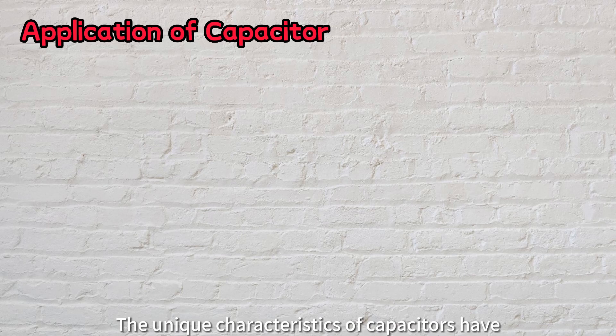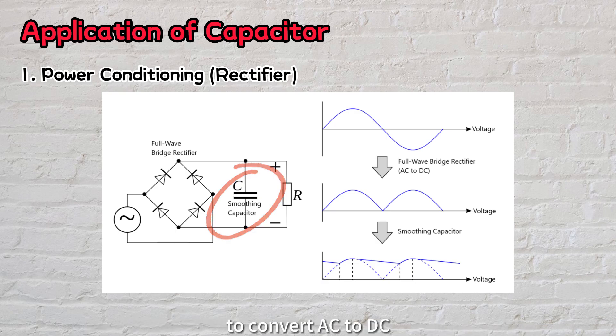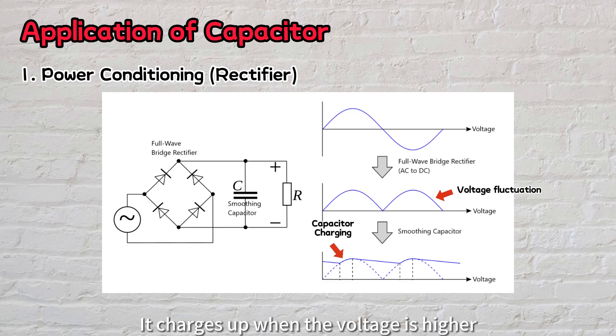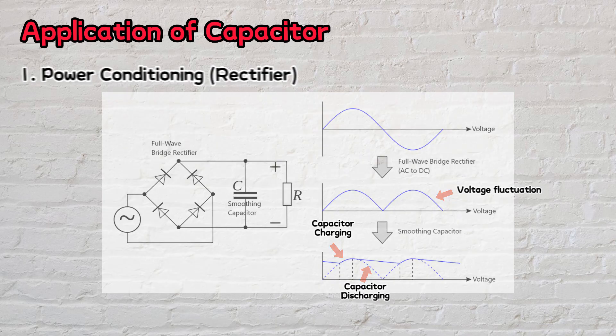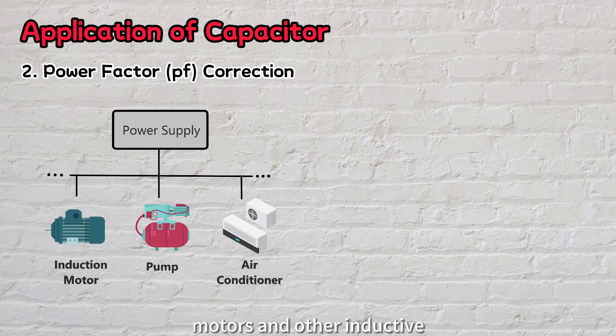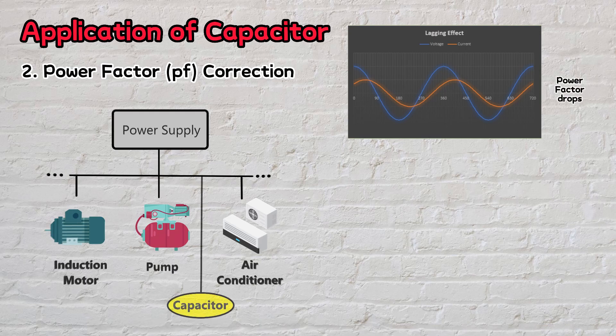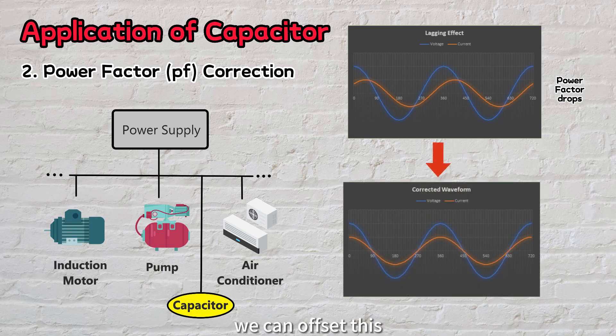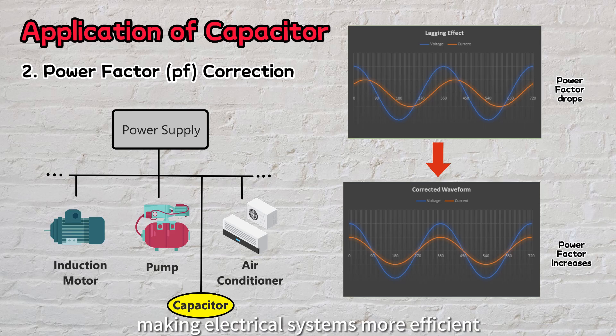The unique characteristics of capacitors have made them incredibly useful in many different ways. For example, in power conditioning, capacitors act as an essential component in rectifiers to convert AC to DC. Capacitors help in smoothing out the voltage fluctuations — they charge up when the voltage is higher and discharge when the voltage is low to boost the voltage, ensuring a steady power supply. Power factor correction is another important application of capacitors. In factories, motors and other inductive loads can cause the current to lag behind the voltage, resulting in a drop in power factor. By installing a capacitor that provides a leading effect, we can offset this lag and bring the current and voltage back in phase, improving the power factor and making electrical systems more efficient.